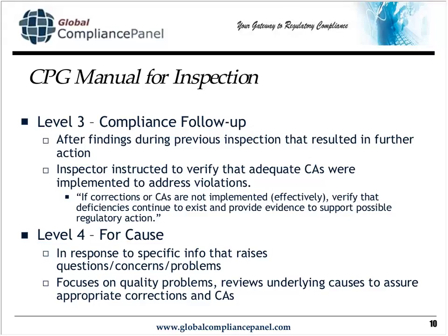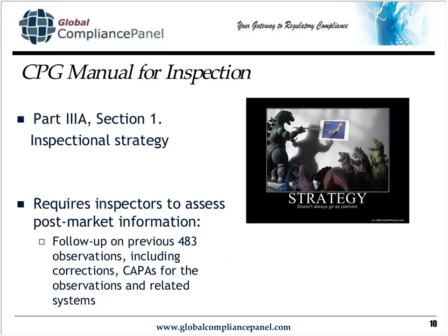And they will go near booths or just overhear what people are saying. And if there is documentation of unreleased products or documented claims that are not warranted to come out, the agency will actually come to your firm with that documentation to follow that up. That's a for cause inspection. During this inspection, they're not going to look at your production and process controls. They're going to specifically look at the reason that brought them there, the document that brought them there.